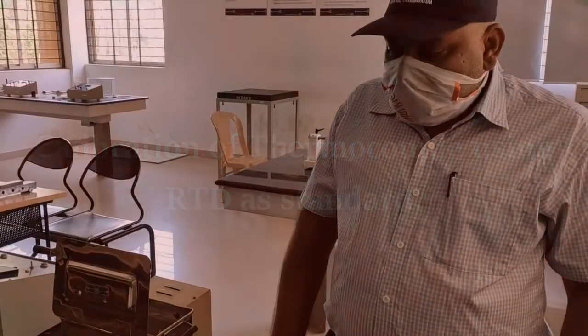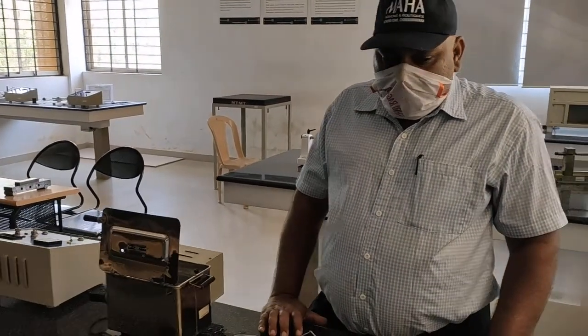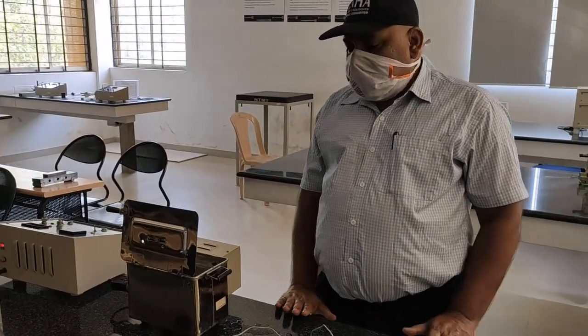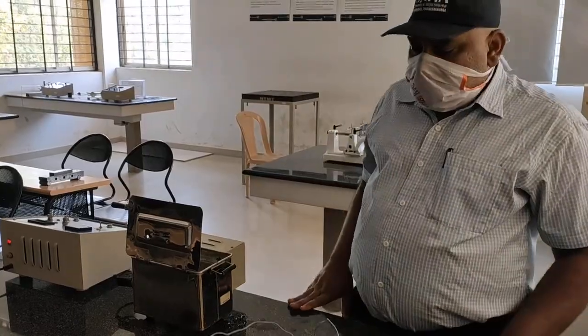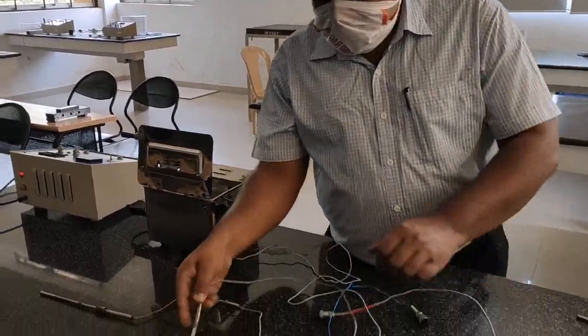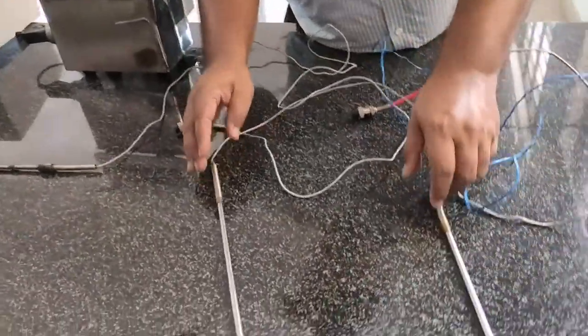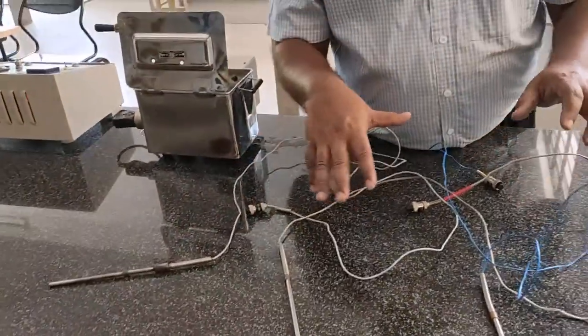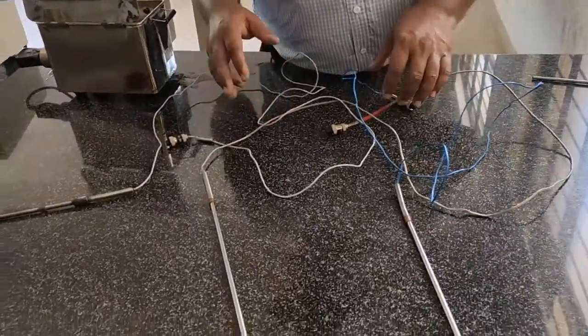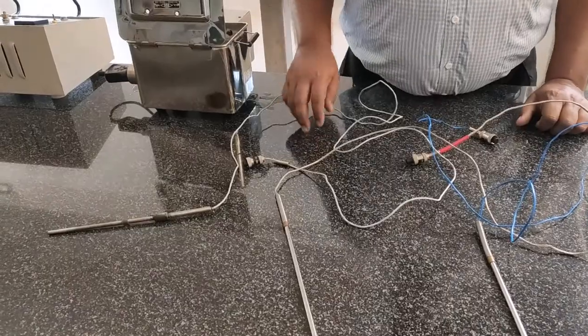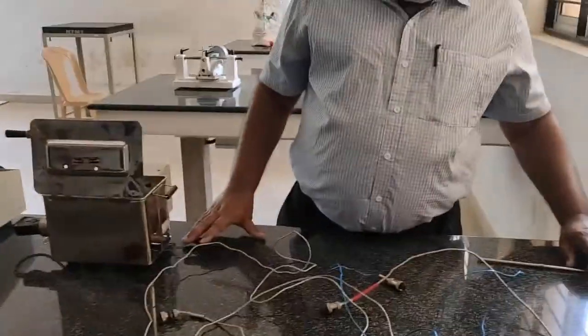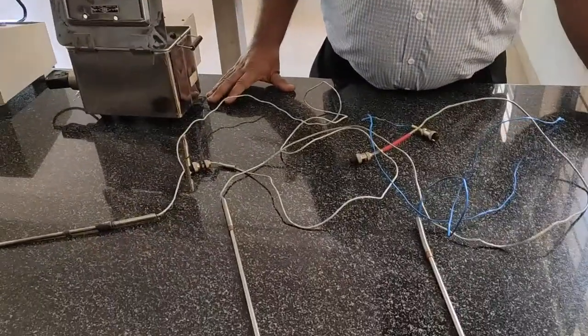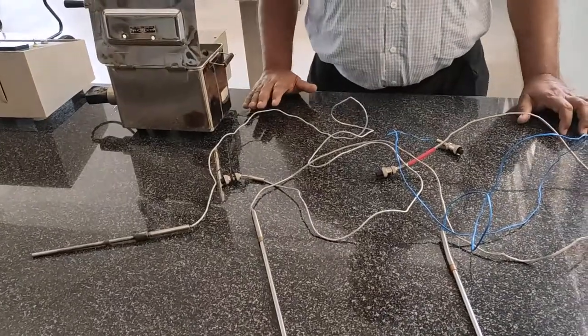Students, we have a different set of calibration setup. We have one more unit, what we call the thermocouple, the calibration of thermocouples. You can find these are the different thermocouples. They have different color coding, and this color coding represents different types of thermocouples. Generally we use them in industrial furnaces, where we try to maintain the temperature of the process.